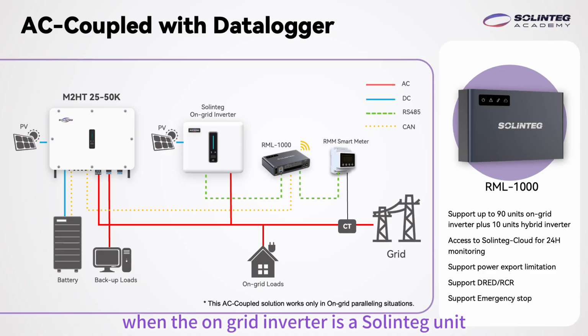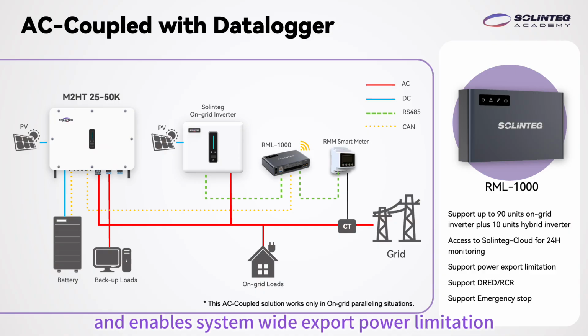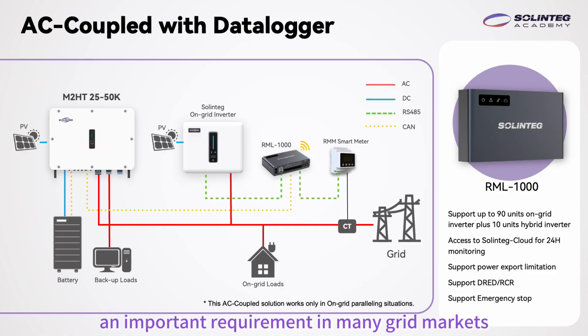When the on-grid inverter is a Solinteg unit, the system can be taken a step further by adding the RML 1000 data logger. This unlocks a higher level of system intelligence and control. The data logger acts as the central hub for the entire system.